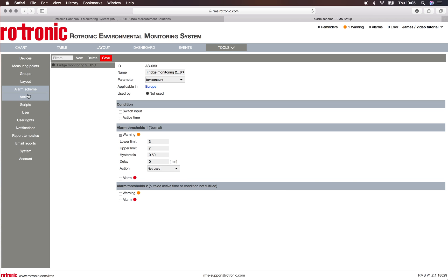I'm interested here in the normal working period, so I can put a warning. The lower limit is three, the higher limit is seven, hysteresis of 0.5, delay of zero — no problem. I can also choose an action; here it's not used because there is no action that has been set up. Please see the relevant video to find out more information about this.